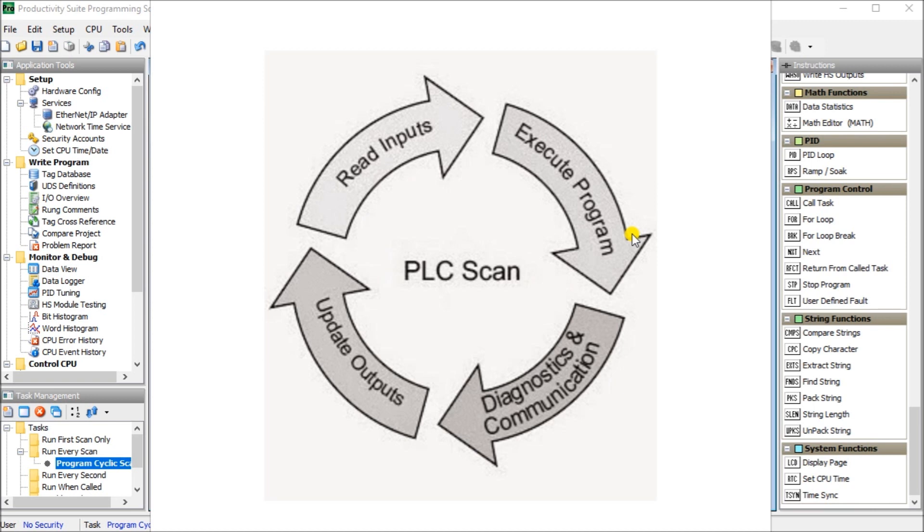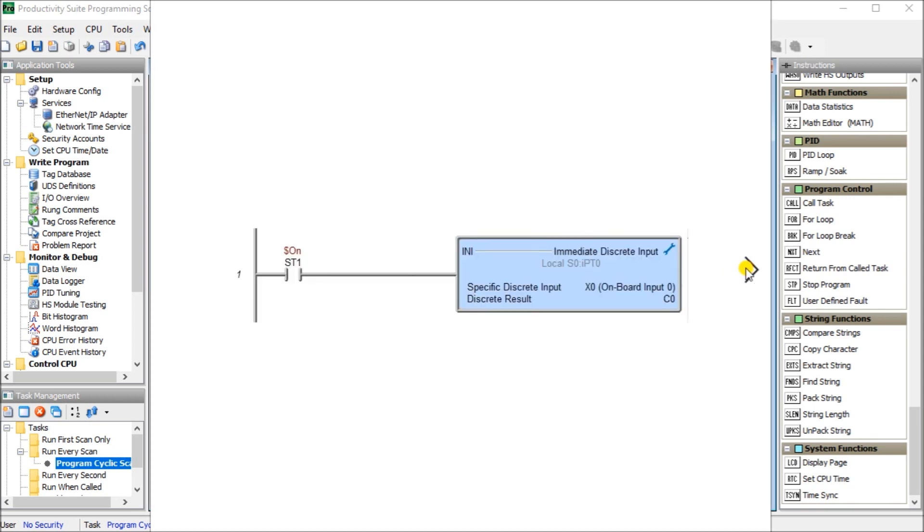PLC scan read inputs. All of the physical PLC inputs are read at least once during each scan. The status of these inputs can then be used in the ladder logic program code. Depending on the controller used, an immediate update can be used if the condition of the input changes within that program scan.